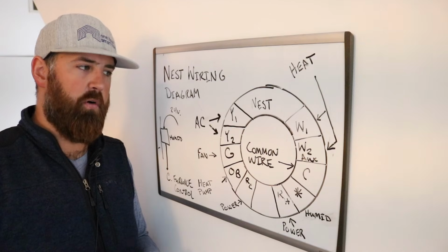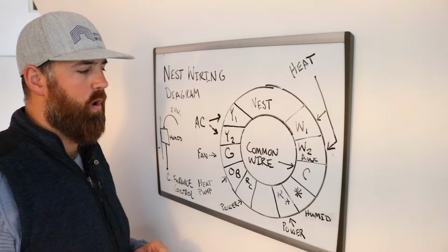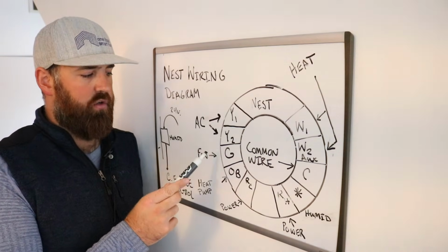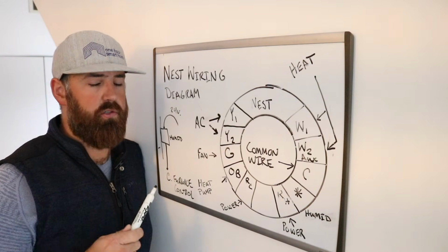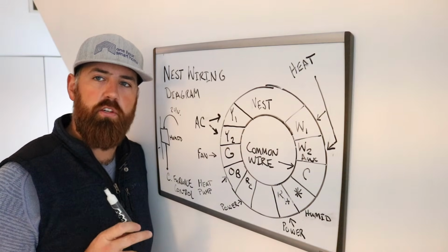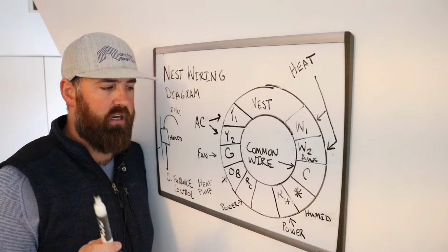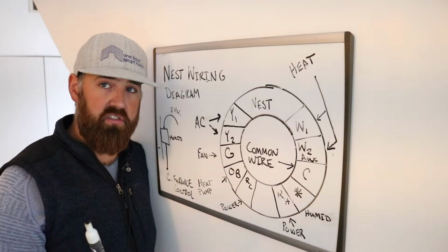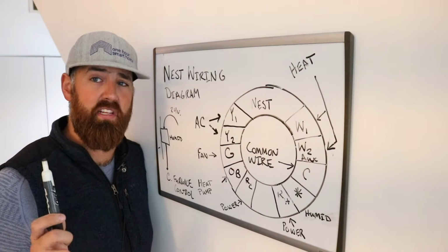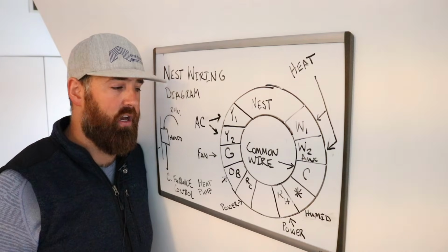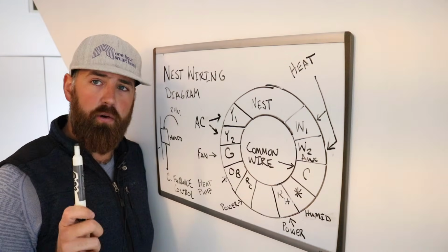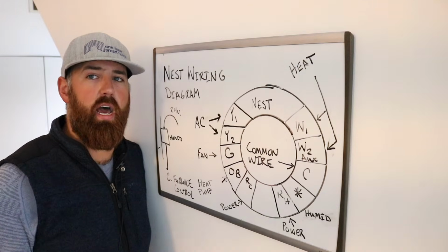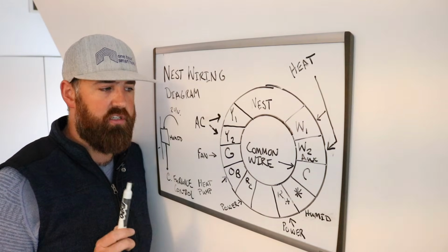Or several of them, on how you can add a common wire. We've got one that shows you how to do it using your G-wire, but then you lose your fan control. We've got another that shows you how to connect a common wire by just adding another wire, which is a pretty complicated process—if your thermostat's not close, you have to run wires through walls and all that. Then we show you probably the simplest way to add a common wire, which is using a common wire transformer.